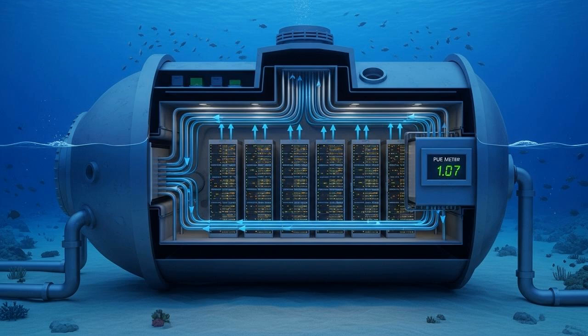In these systems, seawater is piped through radiators attached to the server racks. The server heat is transferred to the cold water, which is then harmlessly discharged back into the ocean. This is way more efficient than air cooling, because water is a much better conductor of heat.